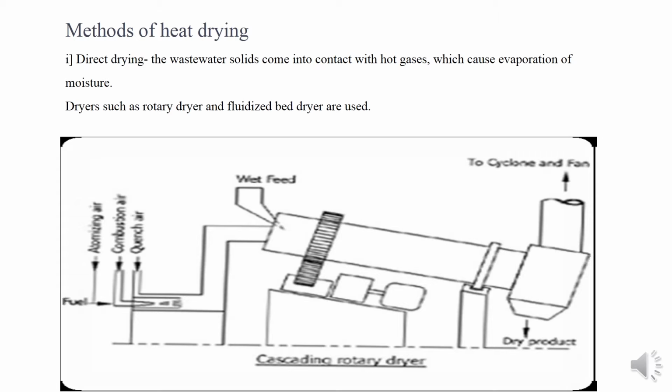Auxiliary components of the drum dryer system include a mixer for blending raw dewatered sludge and recycled dry sludge, a drum feed screw, a furnace with a fuel burner for heating the air, a cyclone and scrubber for separating particulates from the hot exhaust gas, a heat exchanger, a dry sludge extraction screw, and a storage silo for the dried sludge. Now let us see how the system works.